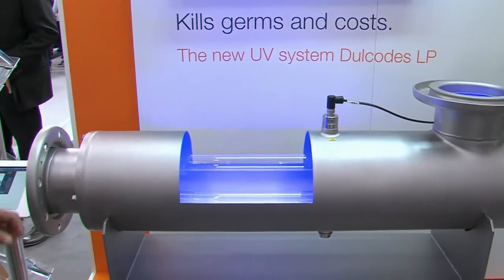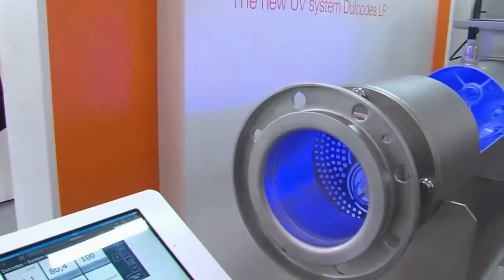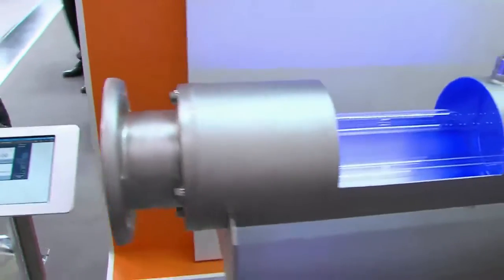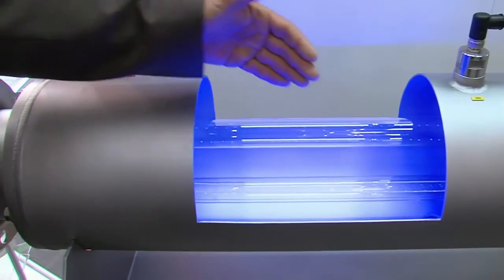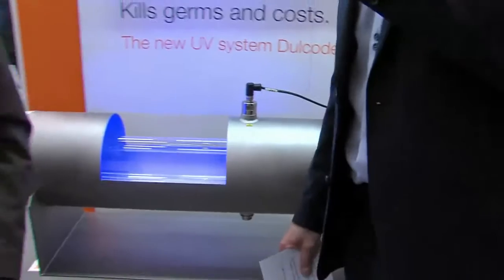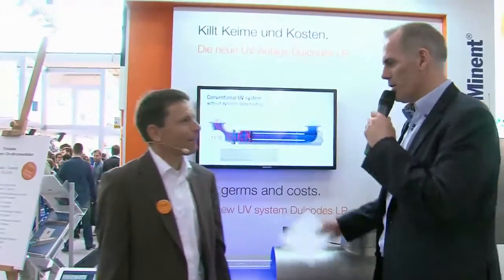The UV lamps themselves are positioned in a UV reactor which is mostly made of stainless steel. We have an inlet and an outlet, and the water flows in through the inlet. Here we already see a very important part of the system, which is the so-called turbulence plate. The water flows through the chamber, is exposed to the UV, is disinfected, and then comes out at the outlet — safe, disinfected drinking water.